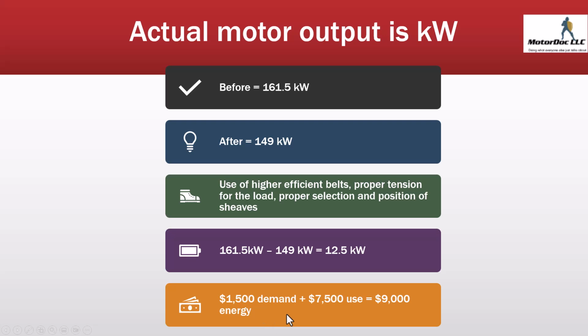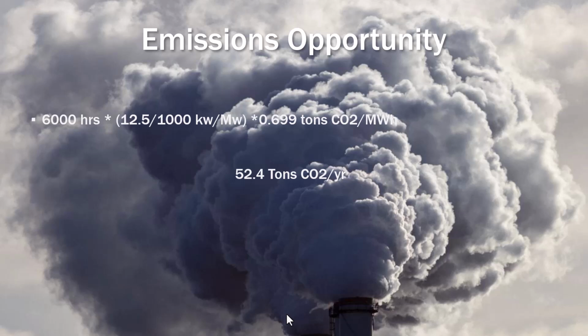Now, I remember the cost associated with this, and we paid for it almost immediately, while also reducing 52.4 tons of CO2 without snapping shafts on the motor anymore, without destroying the bearings, and because there were 14 of these machines, basically eliminating the faults associated with them. So they weren't failing every 6 months anymore. Huge impact cost-wise. The cost avoidance was significant, but management didn't really pay attention to that because cost avoidance isn't on the P&L, but energy sure is, and we were able to show them an immediate, on-the-spot difference, and that had the bigger impact.